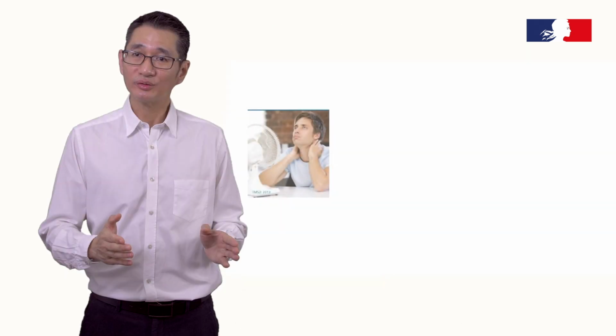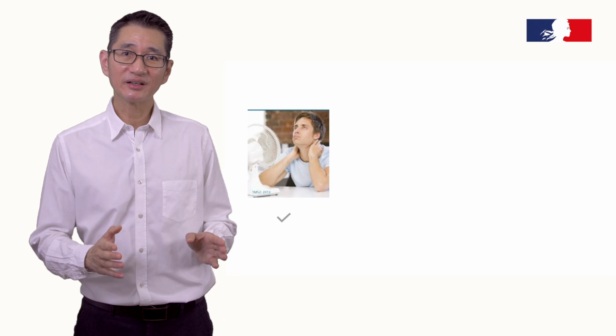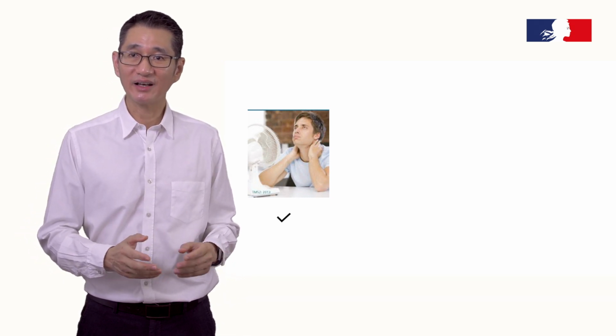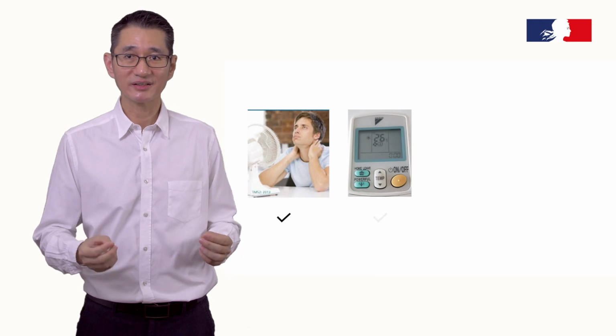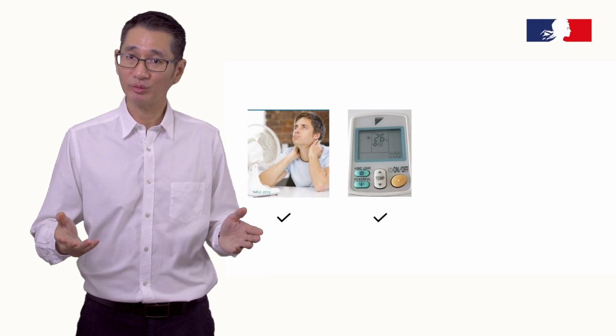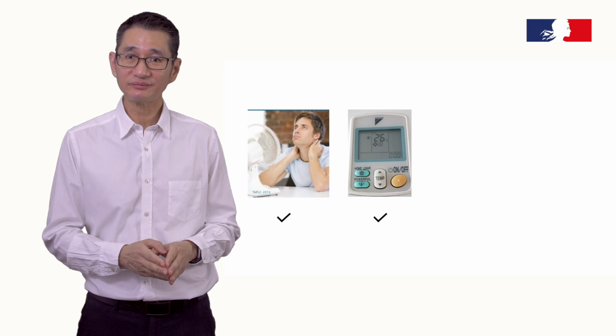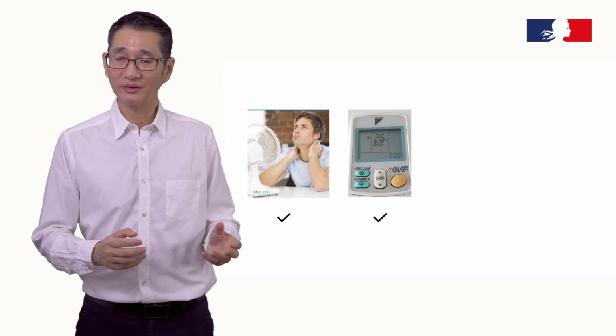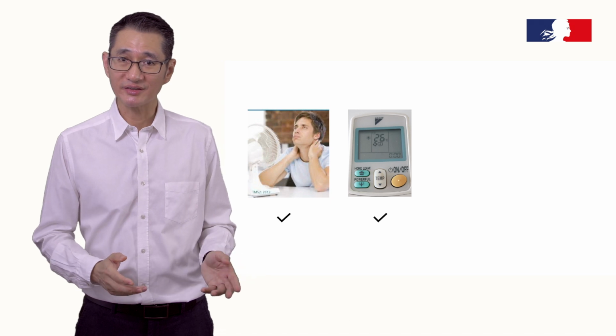In tropical housing, air conditioning is only required infrequently if our homes were designed right. If we need to switch on air conditioning, consider combining it with a fan. In combination with a fan, we can set our air conditioning temperatures to 26-28 degrees, and yet we will feel comfortable. If no fan is available to us, we will be comfortable around 23 to 25 degrees Celsius.